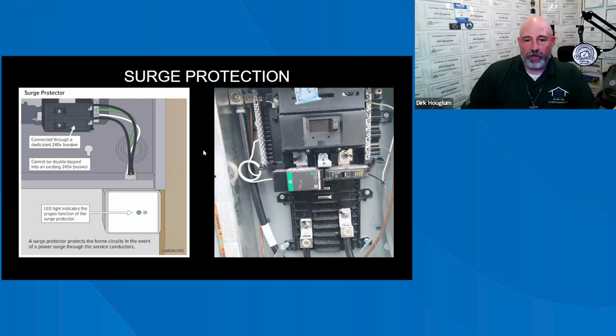What I want to touch on now is something that's new in the 2023 electrical code, which is surge protection. Now that we understand the bonding and grounding, a lot of times you get these surges from the source, which is your power plant, or you could have a lightning strike and it can surge up there. So we want a place where it will not disrupt as many components as possible. It's still recommended to have surge protectors on a lot of your devices. I have one on my computer and my TVs, everything else, so that in case there is a surge of energy, I want it to dissipate that, not my appliances, because why not?